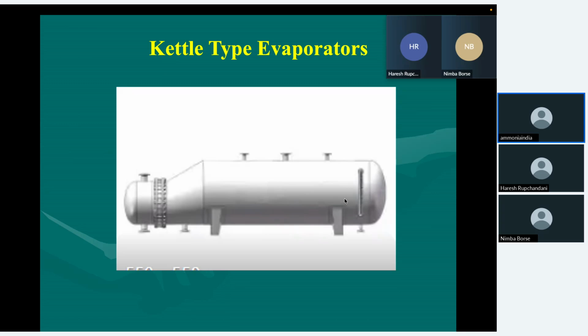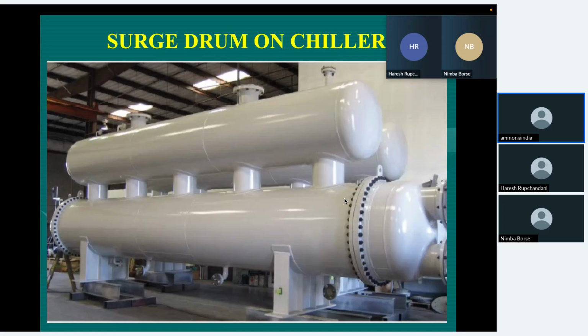There was no surge drum. Directly the outlets were connected. These three outlets were connected to the suction line going to the compressor. I said, this is incorrect design in refrigeration practice. You have to provide a surge drum on top of a chiller. So if you see this next slide, on the chiller, on top of that, there is a big vessel, which is a surge drum.